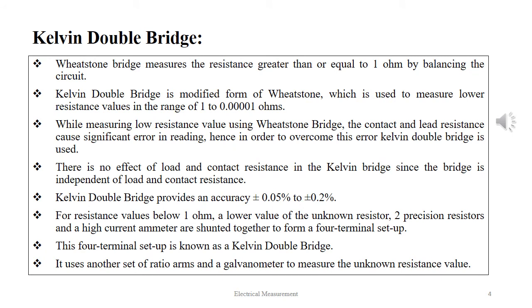The Wheatstone bridge measures resistance greater than or equal to 1 ohm by balancing the circuit. The Kelvin double bridge is a modified form of the Wheatstone bridge used to measure lower resistance values in the range of 1 to 10 micro ohm, or 0.00001 ohm. When measuring low resistance using the Wheatstone bridge, contact and lead resistances cause significant error, and the Kelvin double bridge is used to overcome this. It is independent of lead and contact resistance, providing accuracy of ±0.05% to ±0.2%.